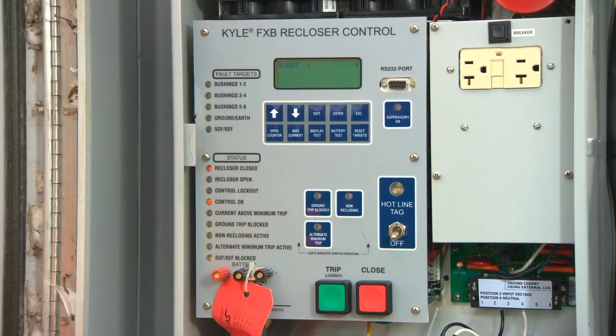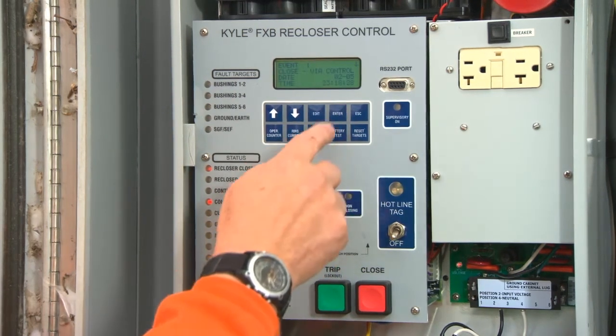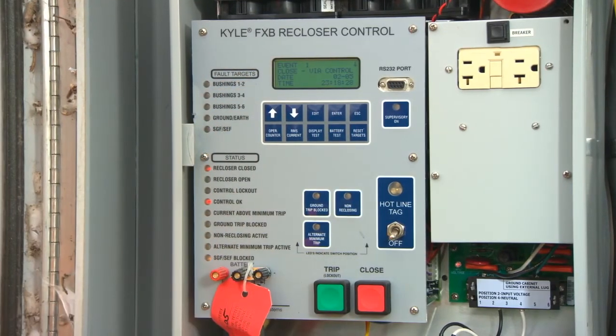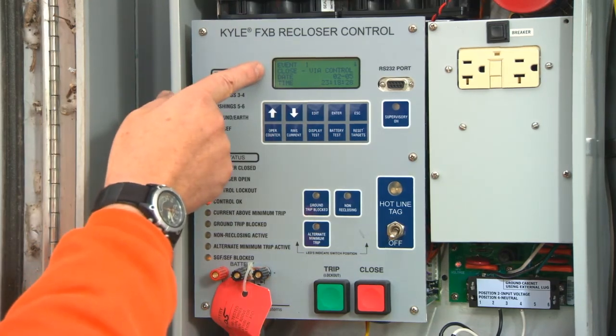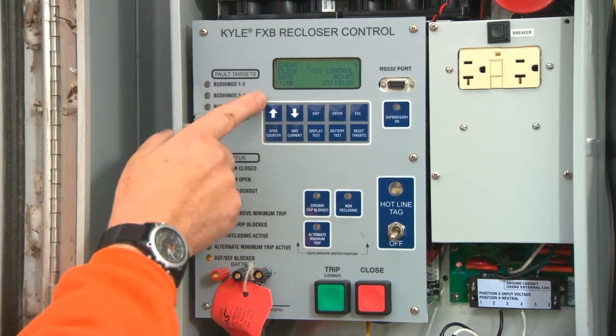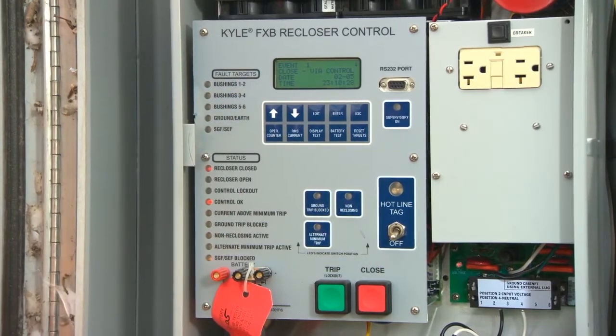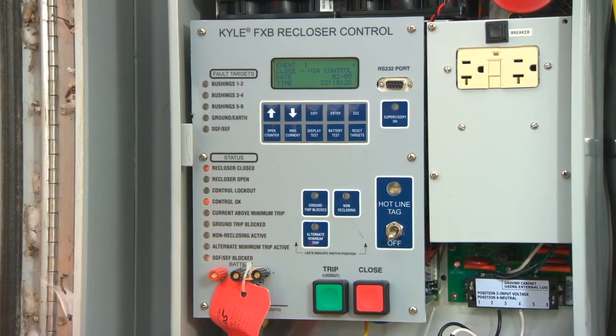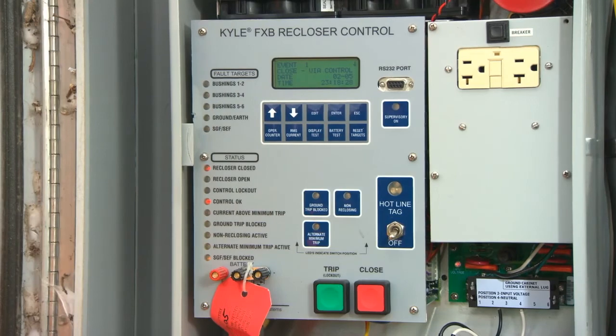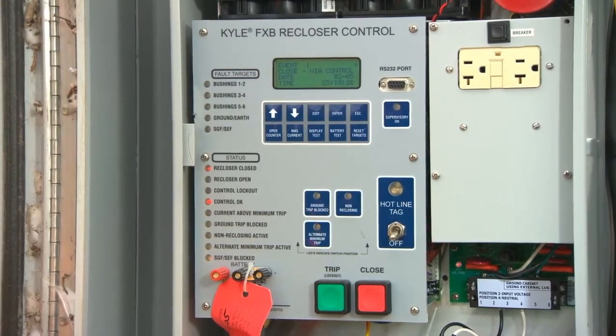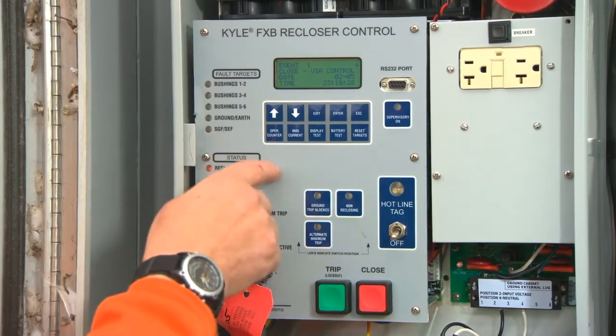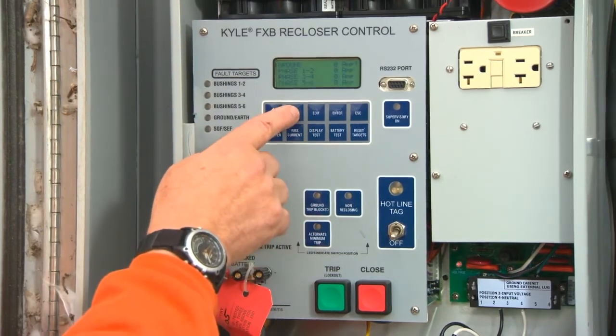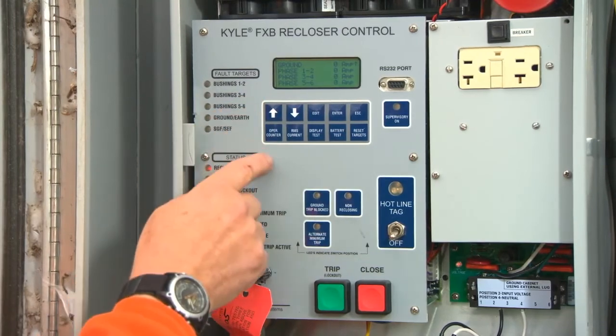The first event displayed here is Event 1, which was the last performed operation by this unit. Pressing Enter again will show an explanation of exactly what happened. As seen earlier, this unit was demonstrating opening and closing the recloser. The final event, Event 1, is shown here as Close via Control. The date and time of this event are also displayed below. Were this a phase fault or ground fault, the phase or phases would be displayed along with the appropriate date and time. Scrolling down from this point will display the phase and ground.